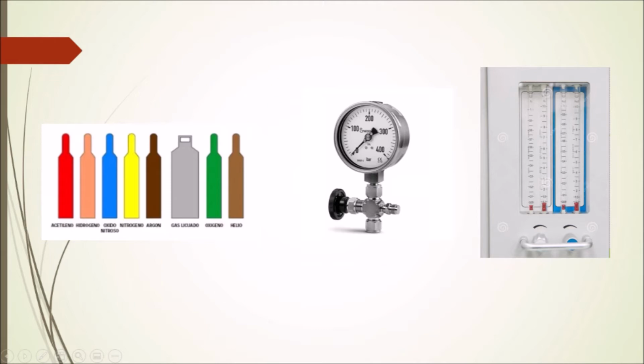Anesthesia machines have an oxygen supply device and an alarm that protects the patient from inadequate oxygen supply. If the oxygen supply pressure drops below about 25 to 30 psi, the unit decreases or closes the flow of the other gases and an alarm is activated.